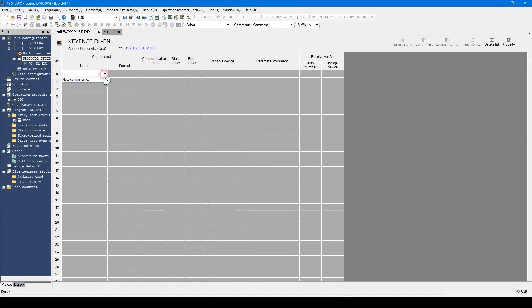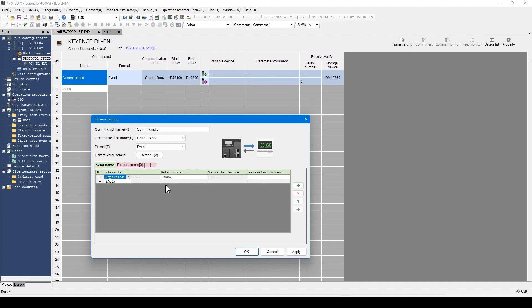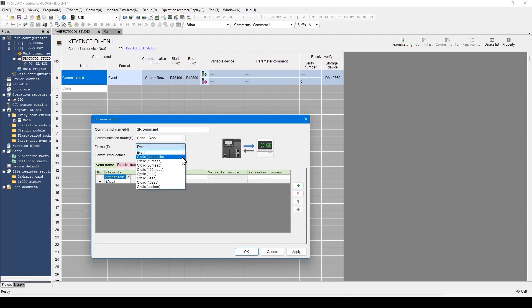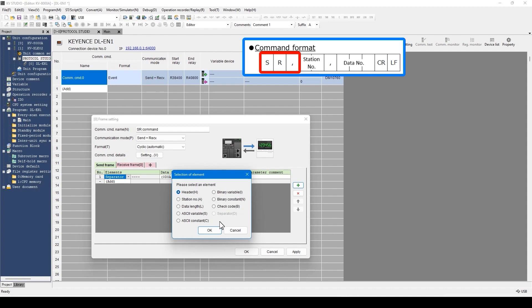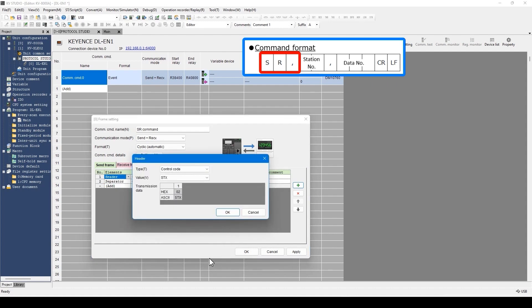Now let's create a command. When the screen to create a command is displayed, the separators set in the default frame setting are already applied to both send frame and receive frame. Therefore, if the default frame is set, you don't have to repeat the same setting when multiple commands are configured. Let's set the SR command. Enter a command name first. Because the PV value needs to be read all the time, select cyclic instead of event. First, set SR comma in the header. Click the plus button, click OK while header is selected. It is a fixed ASCII string — SR comma — so select ASCII, directly enter SR comma from the keyboard, and click OK.